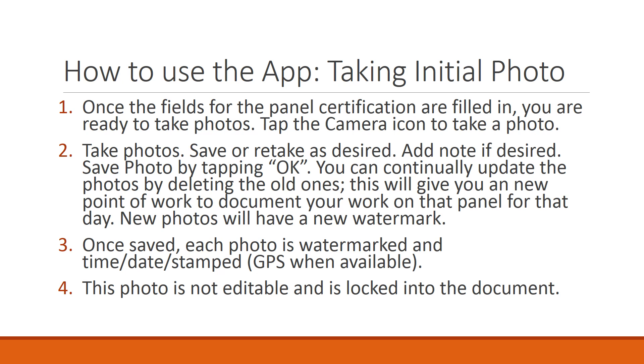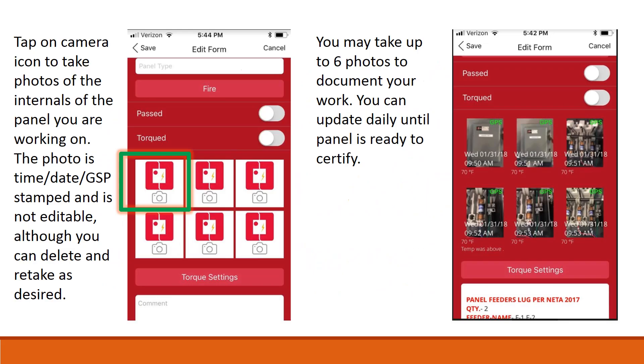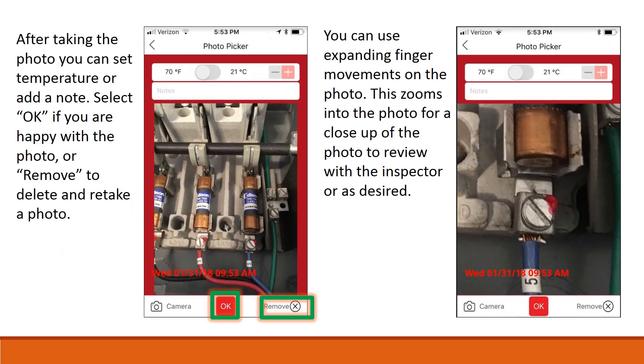Click on the camera icon to take photos of the internals of the panel you are working on. The photo is time-date-GPS stamped and is not editable, although you can delete and retake as desired. You may take up to 6 photos to document your work. You can update daily until the panel is ready to certify. After taking the photo, you can set temperature or add a note. Select OK if you are happy with the photo, or remove to delete and retake. You can use expanding finger movements on the photo to zoom in for a close-up to review with the inspector.